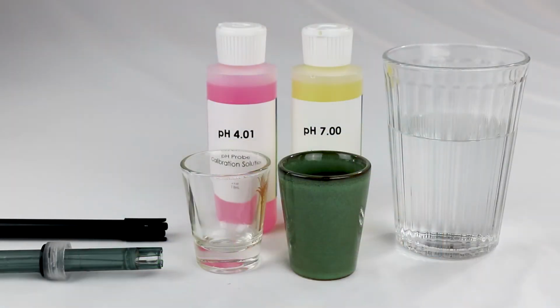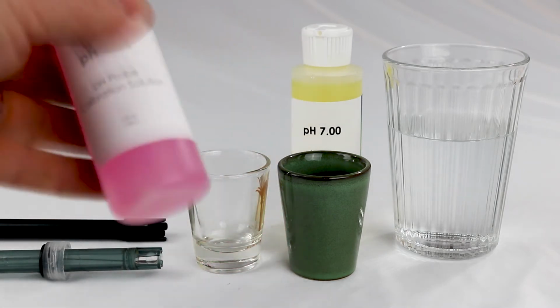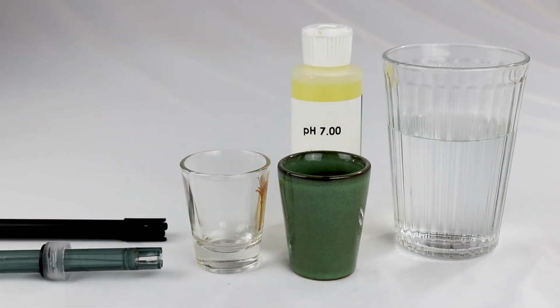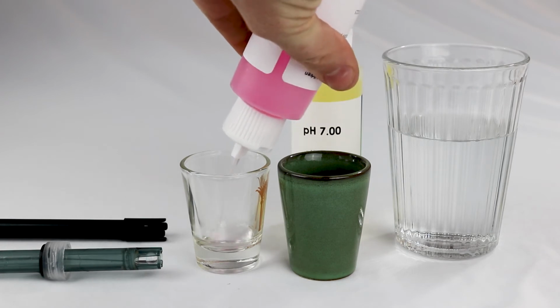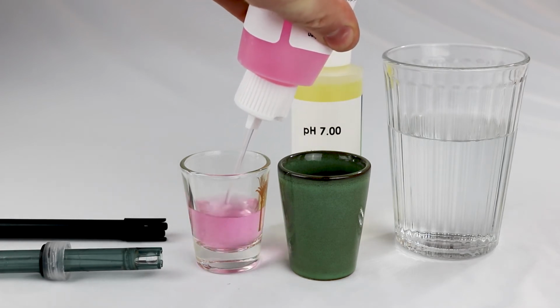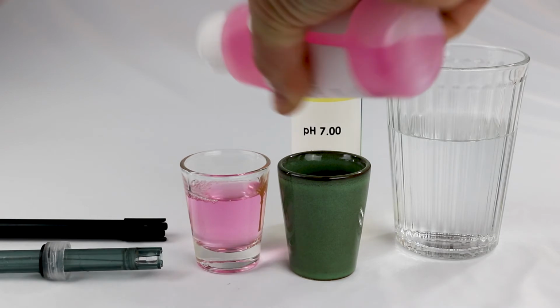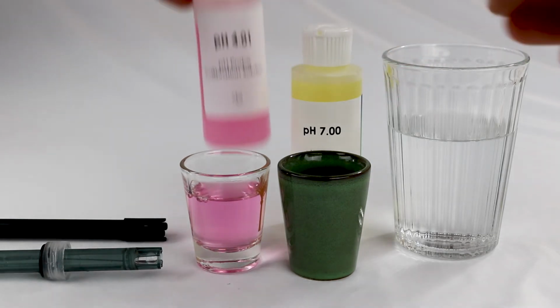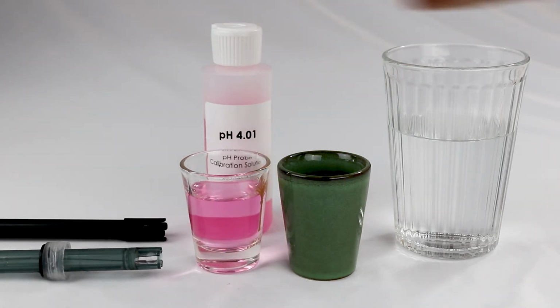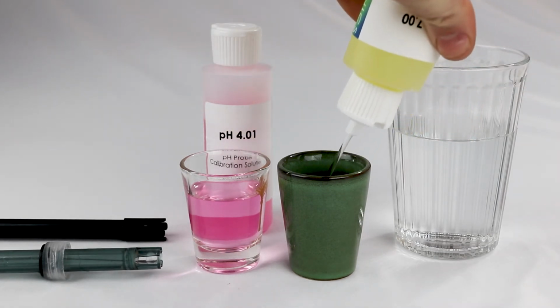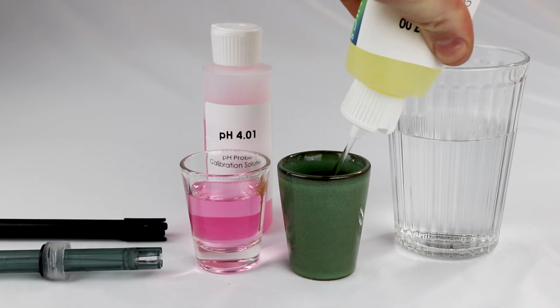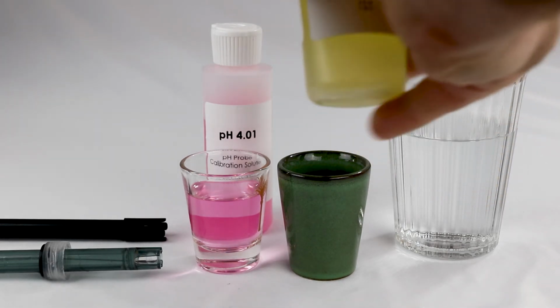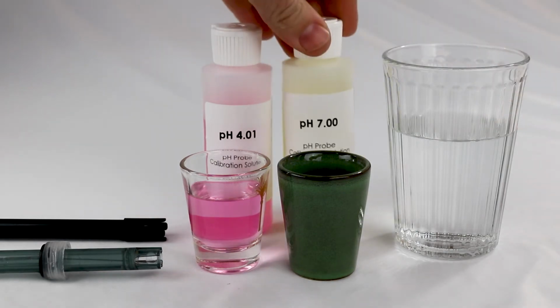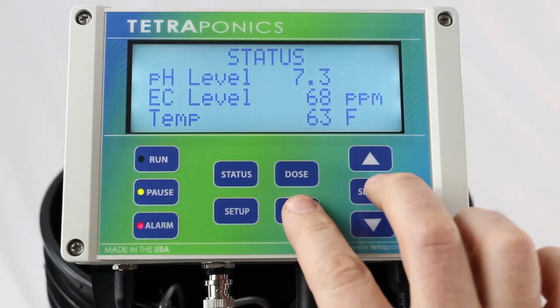The FLORATek 3 uses a 2-point calibration process for the pH probe. Once again, make sure the pH probe and the EC probe are connected to the FLORATek control box. Both of the probes should be removed from the reservoir and at room temperature. Make sure your pH solution is at room temperature and is not expired. Now open the calibration menu by simultaneously pressing the Cal and Select buttons.